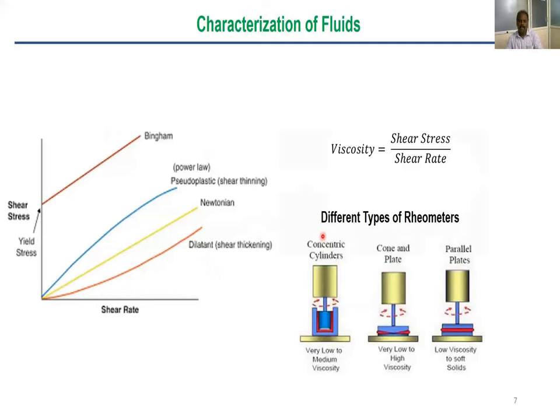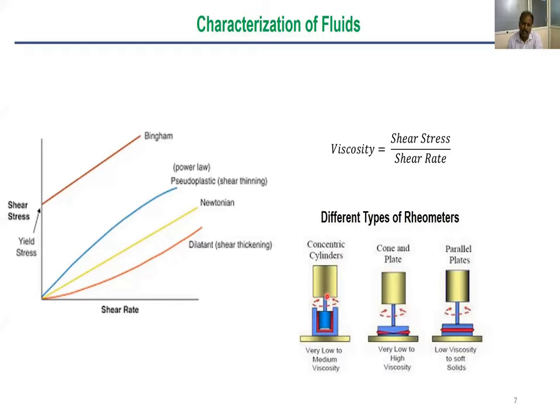To understand what differentiates these fluids, consider shear stress, shear rate, and viscosity — viscosity is the ratio of shear stress to shear rate. Rheometers measure this property. For example, a concentric cylinder rheometer uses a metallic beaker with a spindle inside; the fluid fills the gap and the inner cylinder rotates. Higher torque is required to rotate a high-viscosity fluid, and lower torque for low-viscosity fluids.